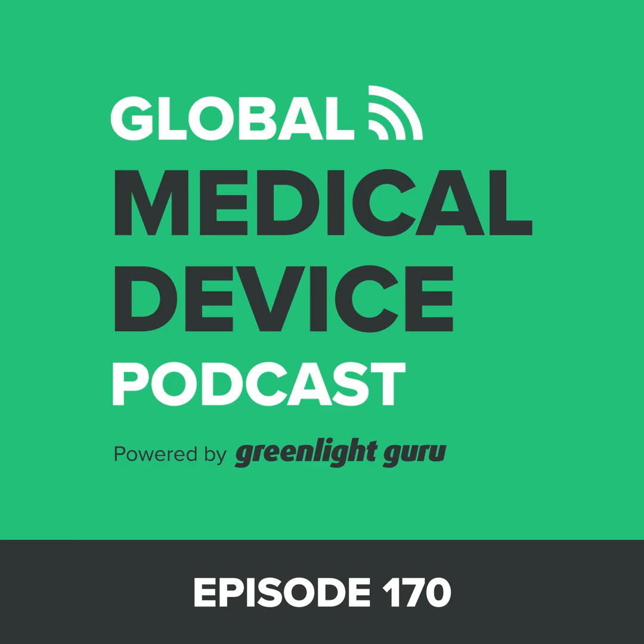No, that's a really great thing to dispel, because I do think FDA is very open to different software development systems. They do want you to document and describe your software development environment. So that would include your process, whether you're waterfall or agile. And I think they want you to describe your code review process. How does software make it into the final production code? But at the end of the day, as long as you have that V&V plan, you can be very open on the design side of things, as long as it's well documented. And then as long as you have a robust V&V plan, then that would still suffice for medical devices.